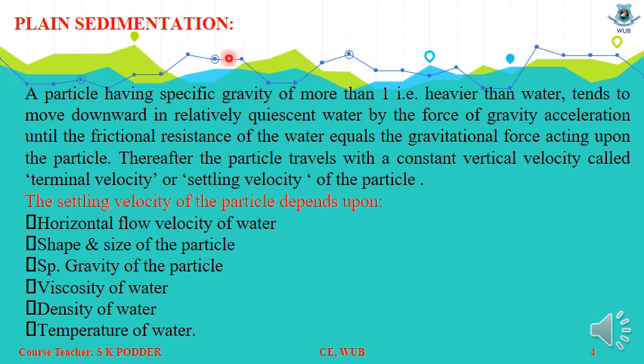Plain Sedimentation. A particle having specific gravity heavier than water tends to move downward in relatively quiescent water — meaning there is no movement of water — by the force of gravity, until the frictional resistance equals the gravitational force acting upon the particle. Thereafter, the particle travels with a constant vertical velocity called terminal velocity or settling velocity.